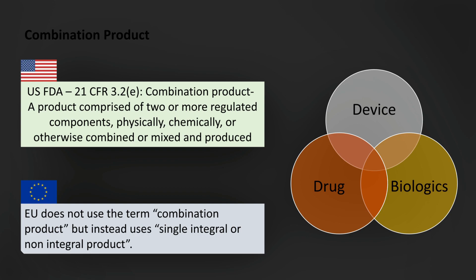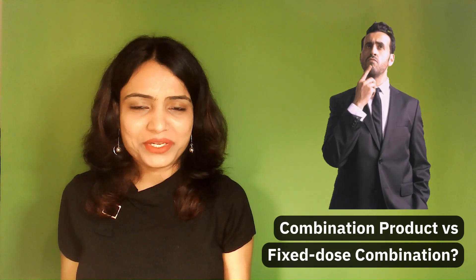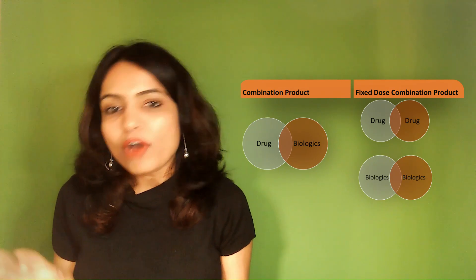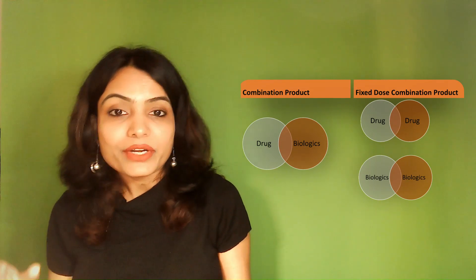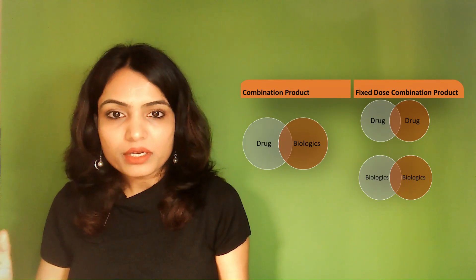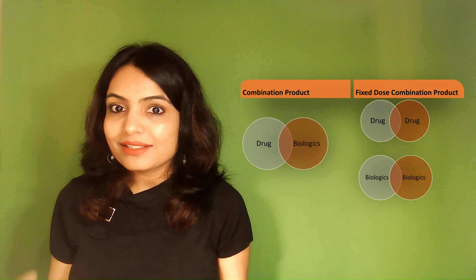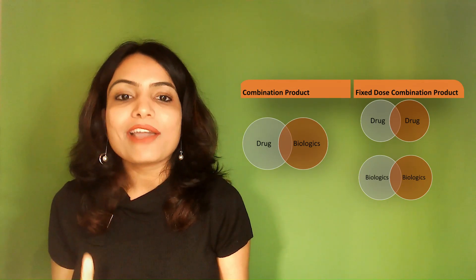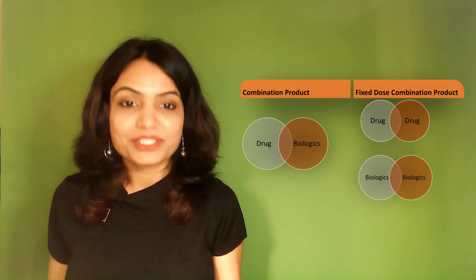So in the US they are called combination products, but in the EU they are called by a different name. We have to be careful not to use the term 'combination products' in the EU context. Now, the next question: are combination products and fixed dose combination products the same? The answer is no. In fixed dose combinations (FDCs) you have one drug combined with another drug, or one biologic combined with another biologic — but not a combination of drug with biologic. If you have a drug combined with a biologic, that falls into the category of combination product, not fixed dose combination.